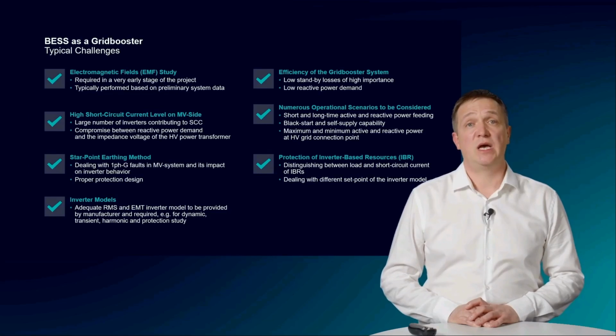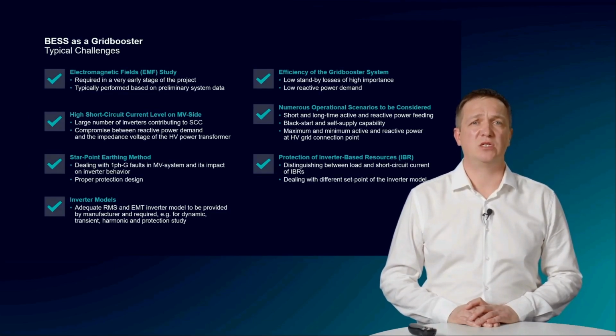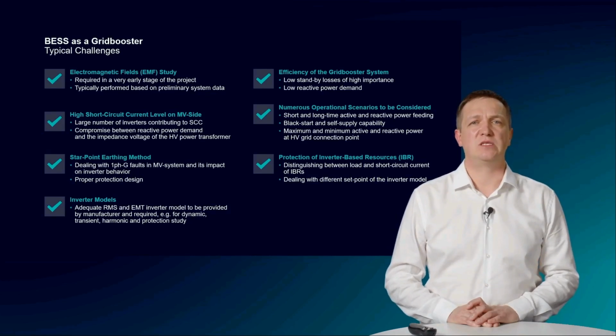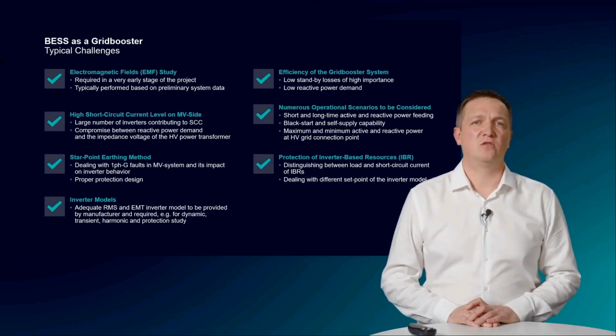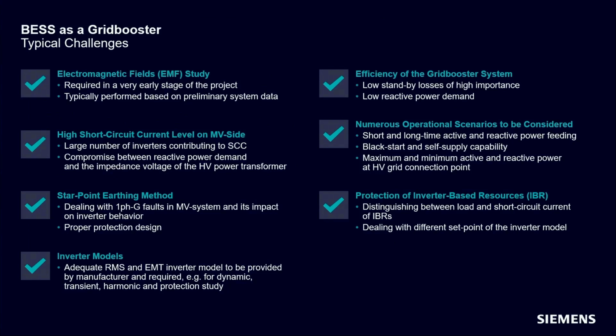If necessary, an aggregation of the grid booster model shall be checked to reduce the computation time and so the project duration. Last but not least, using validated software models, the performance of the protection equipment is to be verified, considering different operation modes and set points of the grid booster units. The study is typically split into elaboration of a protection concept, including the determination of the set points and the software-based verification of the relay settings.